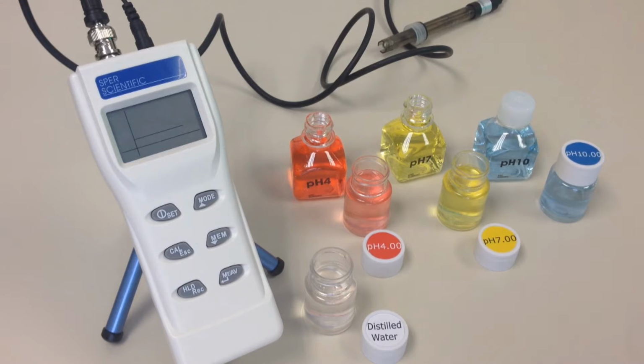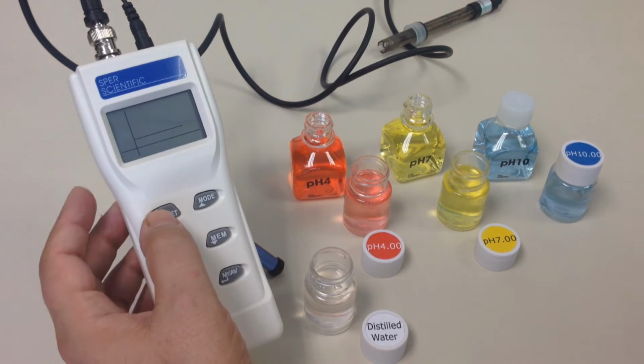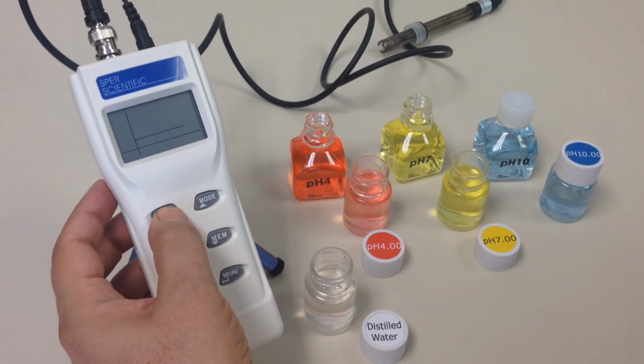I do want to point out in this example we are using standard buffer solution, pH 4 and pH 7. And you could also use pH 10 if you wanted to as well, depending upon what you were actually testing. So the first thing you would have to do, in any case, is turn the meter on. And you do that by hitting this button right here.